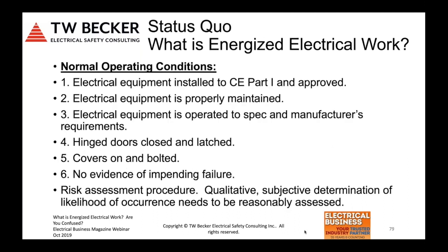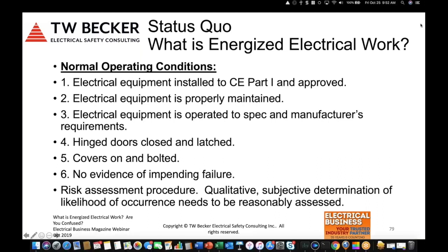As far as the normal operating condition requirements, there are six normal operating conditions: installed to the code, properly maintained, the equipment is operated to the specifications and the equipment manufacturer's requirements, hinge doors are closed and latched, covers are on and bolted, and no evidence of impending failure.